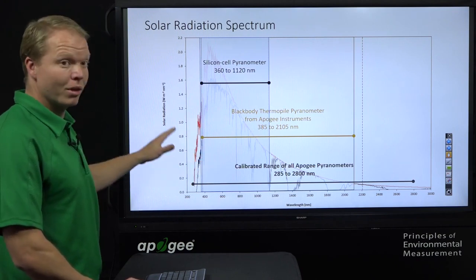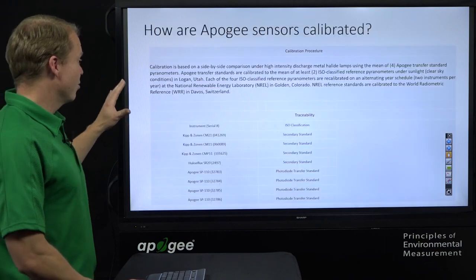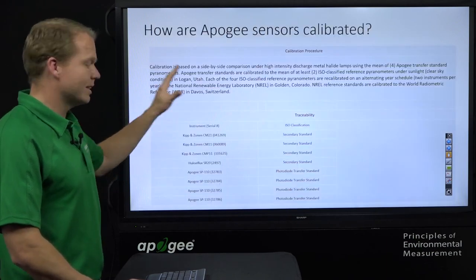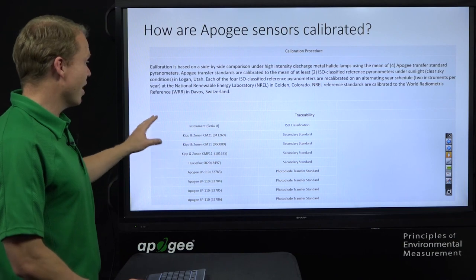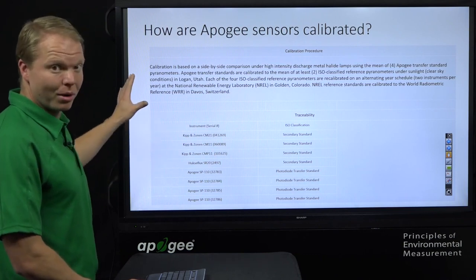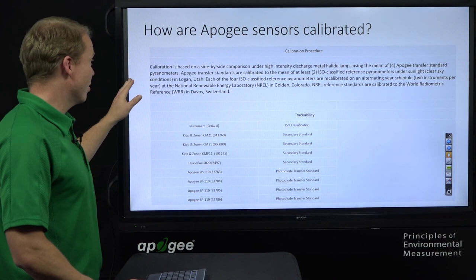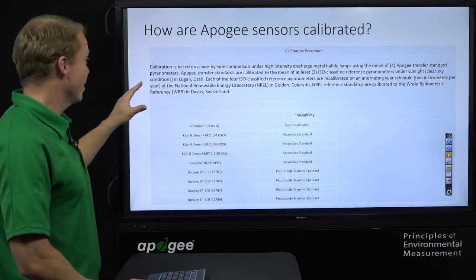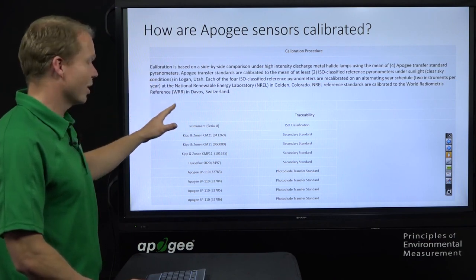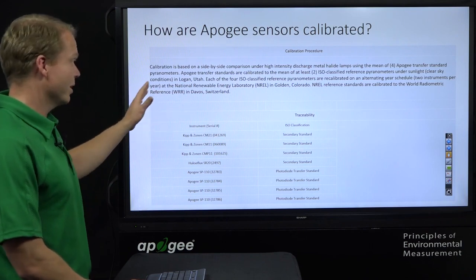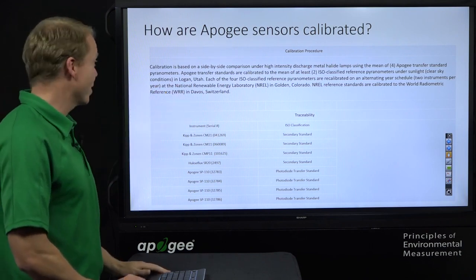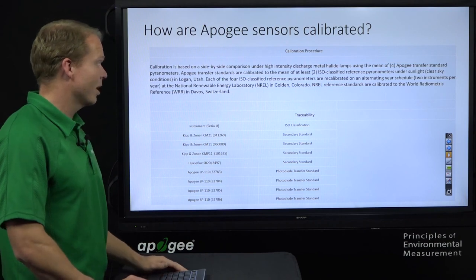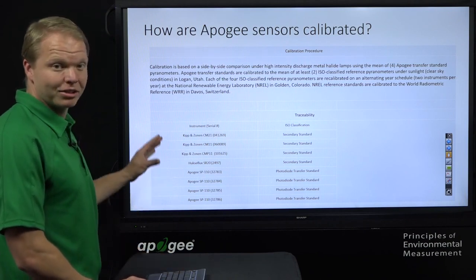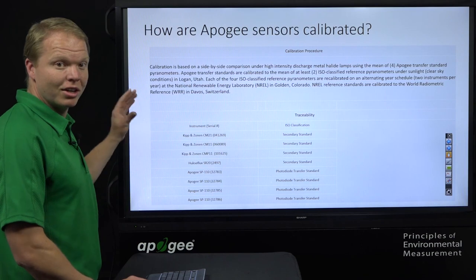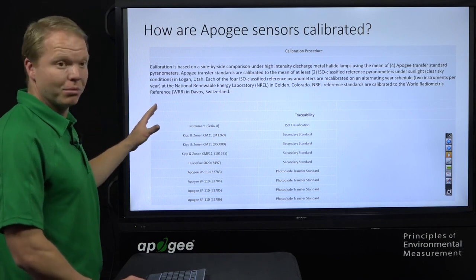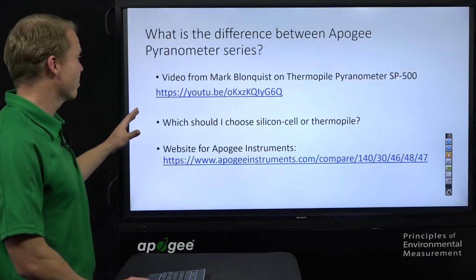nanometers. And the way we do that is we use these ISO classified secondary standards. And these are the standards that we reference all of our pyranometers to. And then we send those ISO classified pyranometers to the National Renewable Energy Laboratory to be calibrated there, which then references back to the World Radiometric Reference in Davos, Switzerland. And so that's how we're able to calibrate our sensors that have a smaller spectral response to match the output of high-end blackbody thermopile pyranometers.